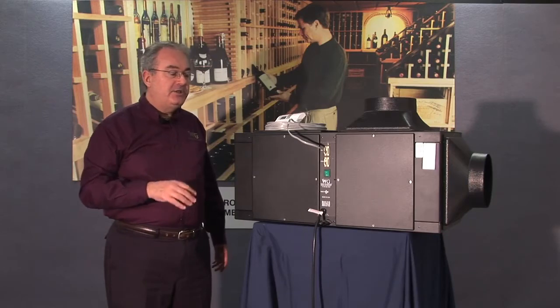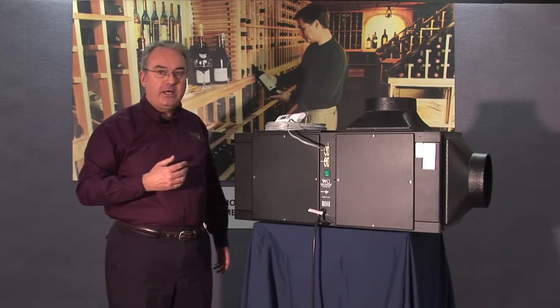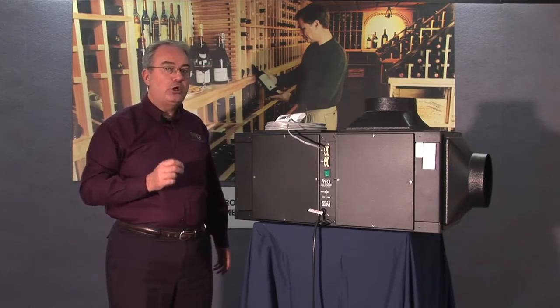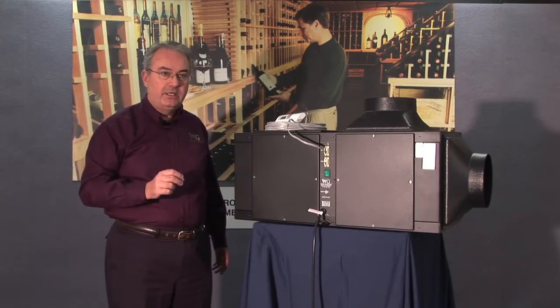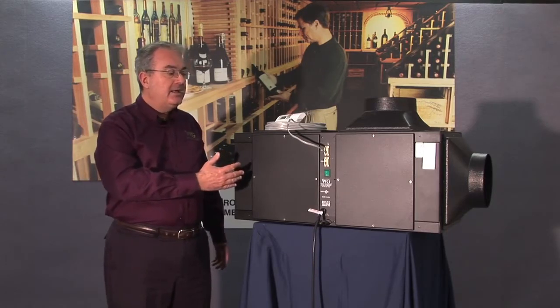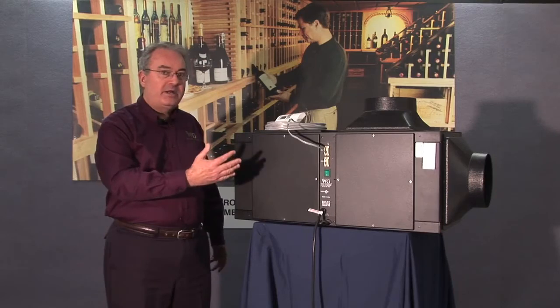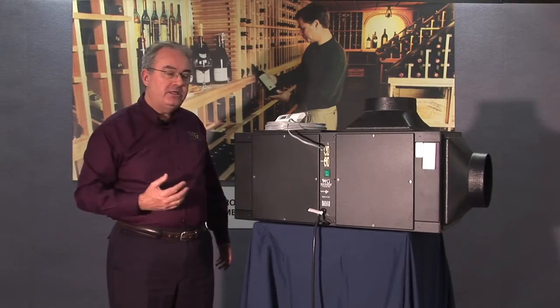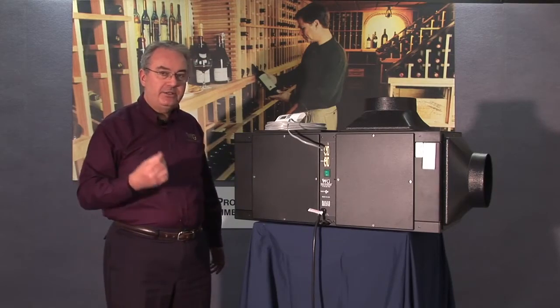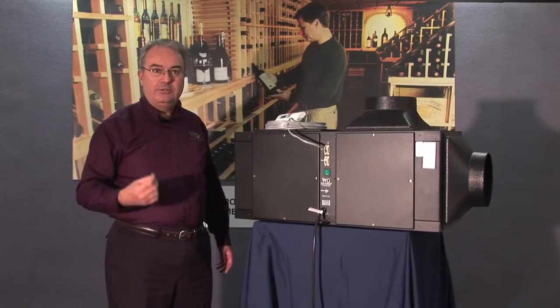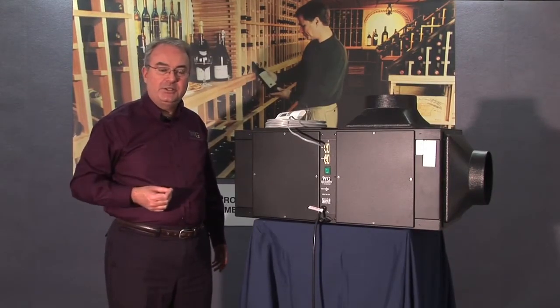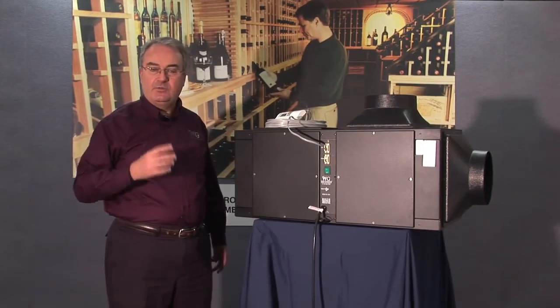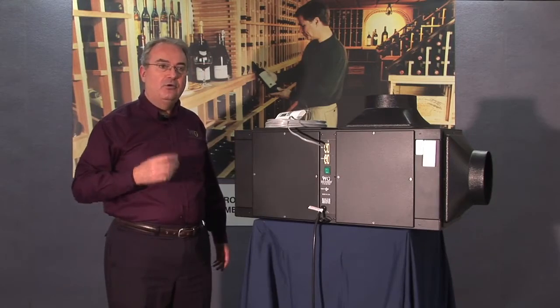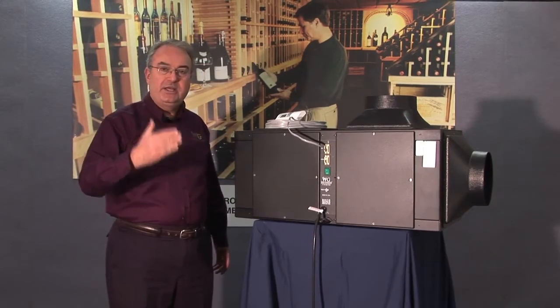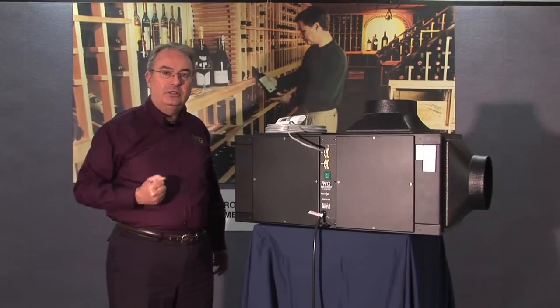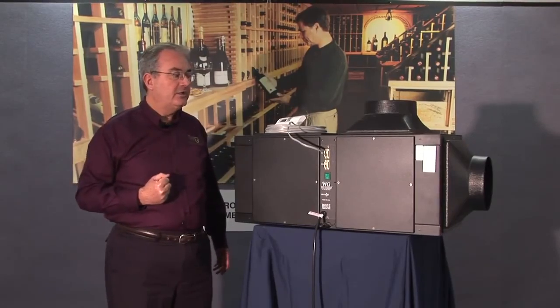I also want to mention that what you see here is the air-to-air unit. We do have a water-cooled version of this unit, which means that on the warm air section, you don't really need to run ductwork to the outside. You can use a flow of water to reject the heat. Ideal for installations perhaps in condominiums, for particularly silent applications, or for installations where for some reason you can't actually make a hole in the exterior wall of the structure.